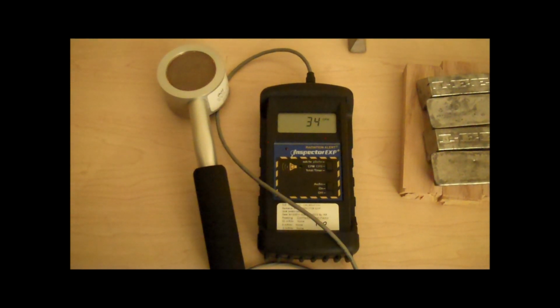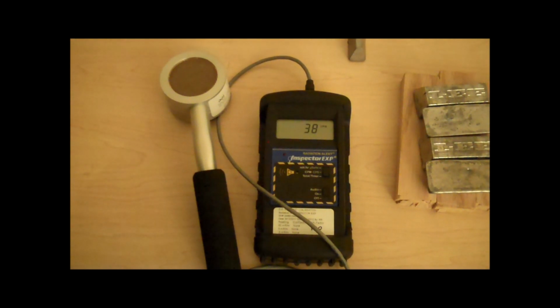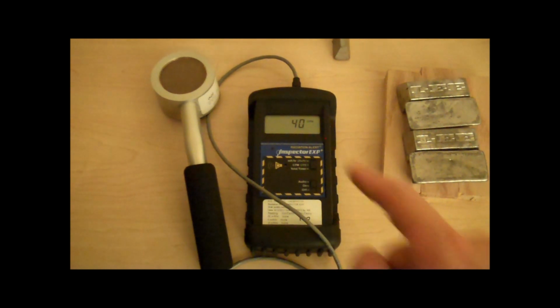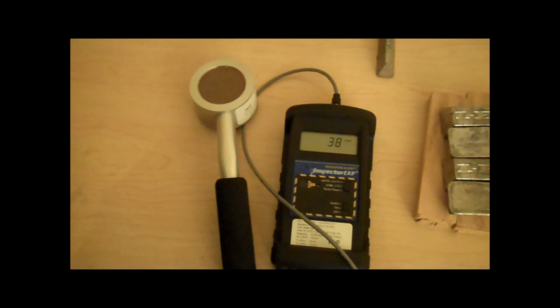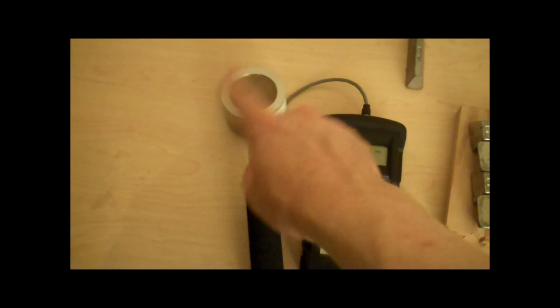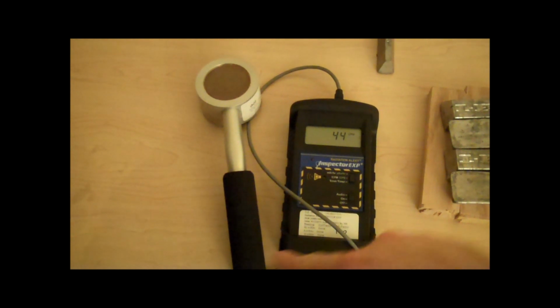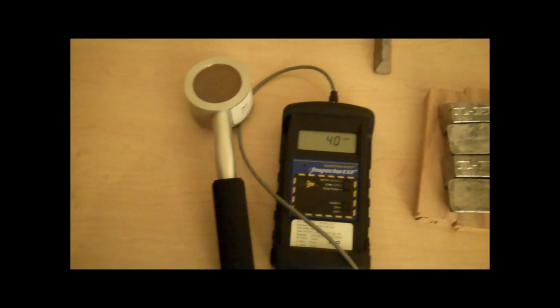For many years, radiation was detected primarily using a Geiger counter. A Geiger detector here with a Geiger-Müller tube on the end. For every single piece of radiation that hits this little detector that it's capable of detecting, a cascade of electrons is generated, completing a circuit. The pulse of energy is then registered on the counter.